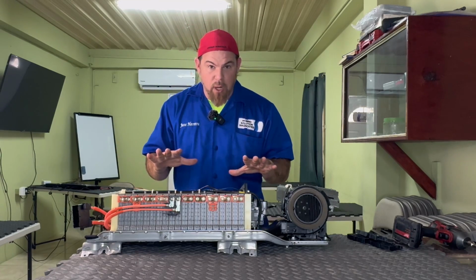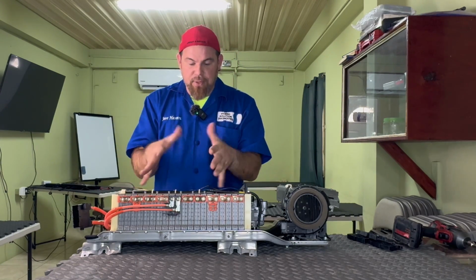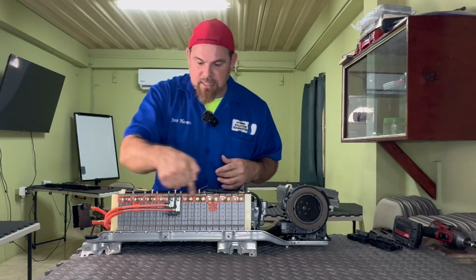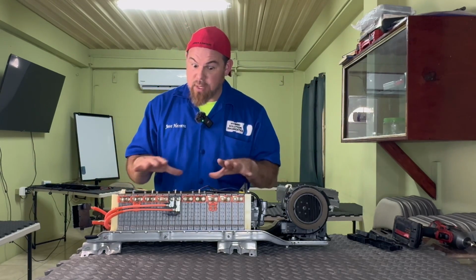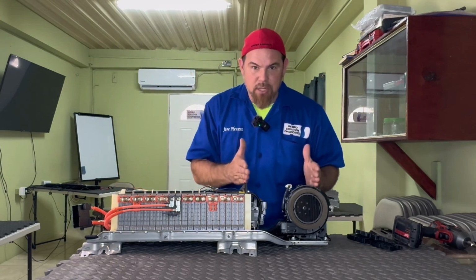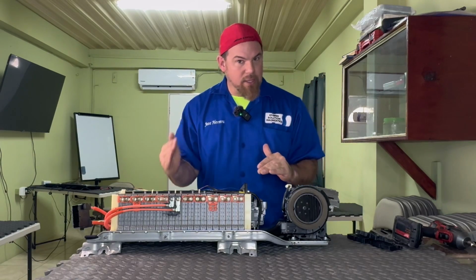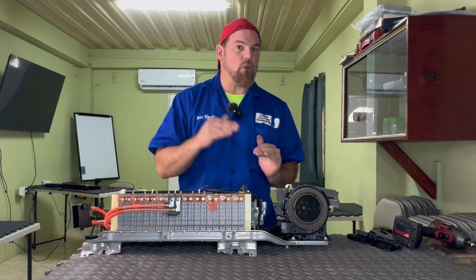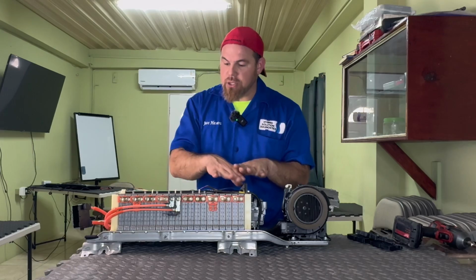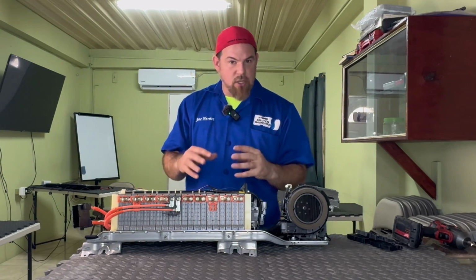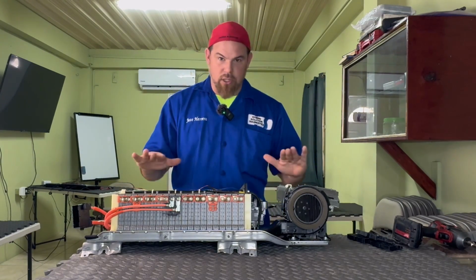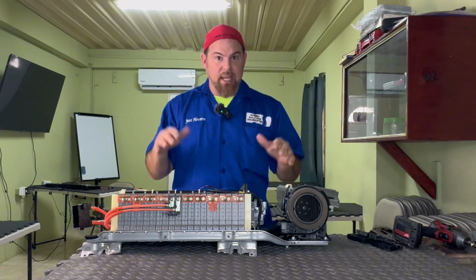So in order to solve this problem, what we need to do is apply a 50% rotation, replace the disconnecting lugs to reduce the resistance as much as we can, and then connect the machine to our prolonged charger for at least 24 hours, and that's how we're going to force rebalance the battery. As long as there's no lost capacity in some of the modules that suffer heat stress, the battery should be just fine. This is how the battery restores its maximum capacity.